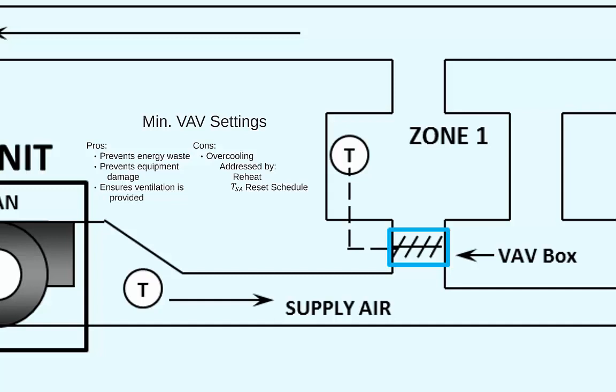The comfort issue that ensues can be addressed in one of two ways. Either we install a reheat capability in our VAV boxes, or we implement a supply temperature reset schedule. Let's talk about the VAV with reheat configuration before we get into reset schedules.